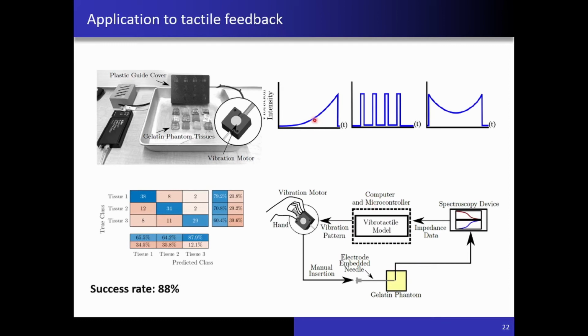We can then assign each tissue to one vibration pattern. Here we have 3. We show this in time and you have the intensity of the vibration. So this is like a ramping up vibration. These are small pulses, and this is one going up and down and back up. So depending on the tissue that the needle tip is going through, the user will feel these patterns and it will help them get real-time feedback of what tissue the needle is traversing at the tip. I have 3 different tissues, and you see the success rate. So this is the tissue at the tip, and this is what the user perceived as being the tissue based on these patterns. And you see that the success rate is relatively good here. Overall, 88% of the time, they were able to classify the tissue based on the vibration patterns they received.